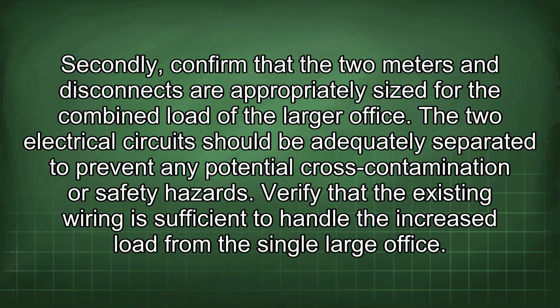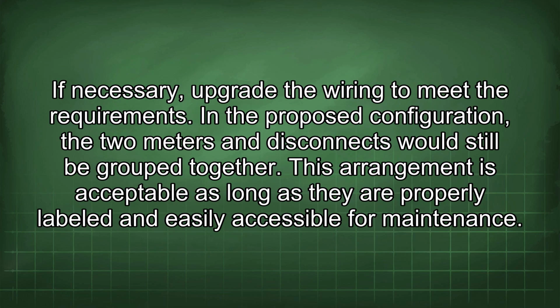The 2 electrical circuits should be adequately separated to prevent any potential cross-contamination or safety hazards. Verify that the existing wiring is sufficient to handle the increased load from the single large office. If necessary, upgrade the wiring to meet the requirements. In the proposed configuration, the 2 meters and disconnects would still be grouped together. This arrangement is acceptable as long as they are properly labeled and easily accessible for maintenance.